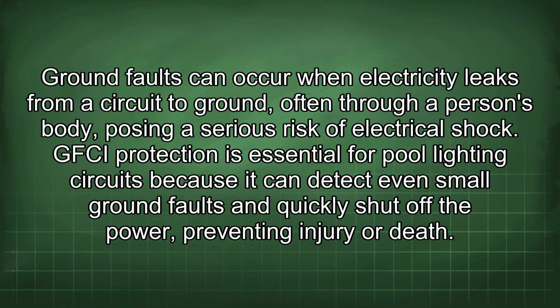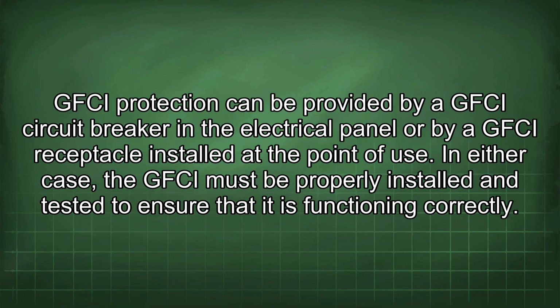Ground faults can occur when electricity leaks from a circuit to ground, often through a person's body, posing a serious risk of electrical shock. GFCI protection is essential for pool lighting circuits because it can detect even small ground faults and quickly shut off the power, preventing injury or death. GFCI protection can be provided by a GFCI circuit breaker in the electrical panel or by a GFCI receptacle installed at the point of use. In either case, the GFCI must be properly installed and tested to ensure that it is functioning correctly.